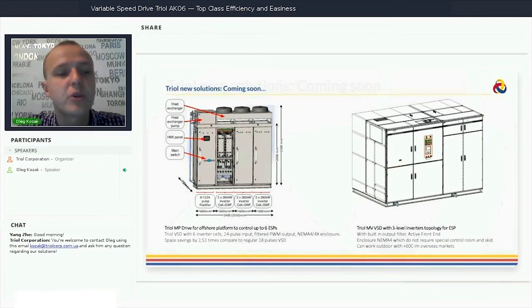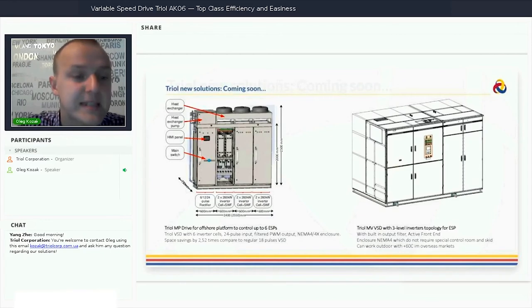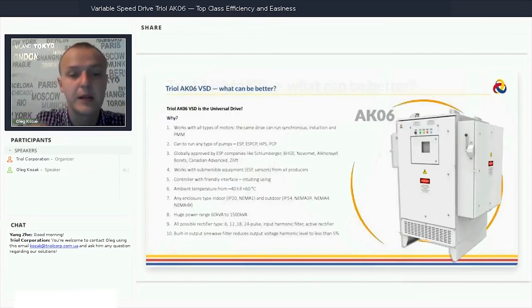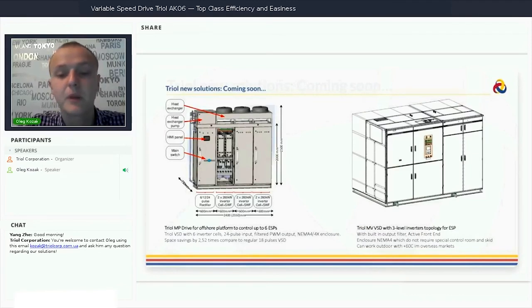On the picture you see the prototype of 3.3 output kilovolts, so it's a big one. For the ESP we expect to have like 1.2 or 2.4 kilovolts. It will be a small one, like the AK06, the same cabinet, like this one in this picture, but it will be a 3 level inverter topology. So you don't need any step up and step down transformer. So it will be a medium voltage VSD which meets your THD expectation, and you don't need any transformer at all.